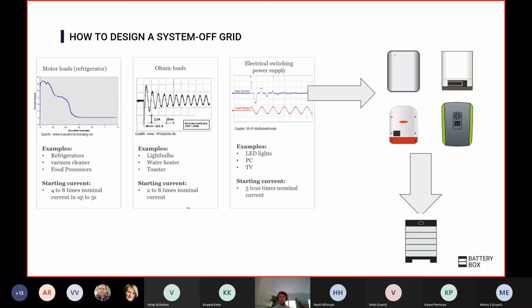And finally, the off-grid systems. We have a document called the minimum configuration list, in which we recommend a number of batteries per type of inverter. These are especially designed for off-grid systems, because this amount of batteries would be able to withstand the surge power, the maximum surge power that inverter can allow.